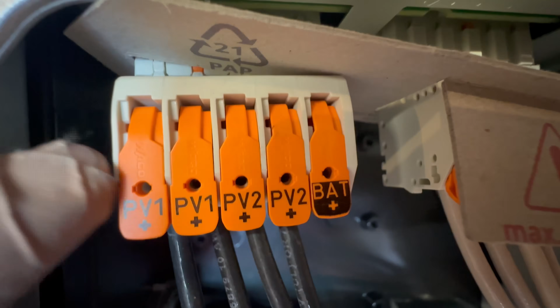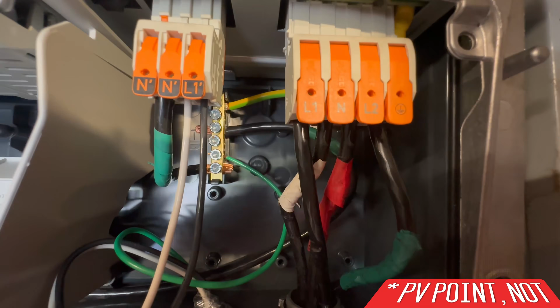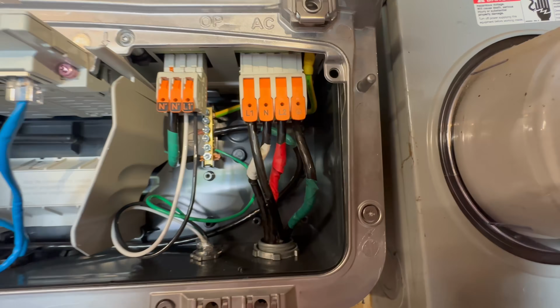All of these connections can take up to number 6 on this class of inverter, the larger class, which I think is like the 8 kW, 10 kW—this is obviously a 10 kW—except for the PV point. The PV point is what Fronius calls the source of power you have when the power goes down and the sun's still out; you can still plug something in here. For the PV point connectors, these only go up to number 8, or at least that's what it says in the manual.